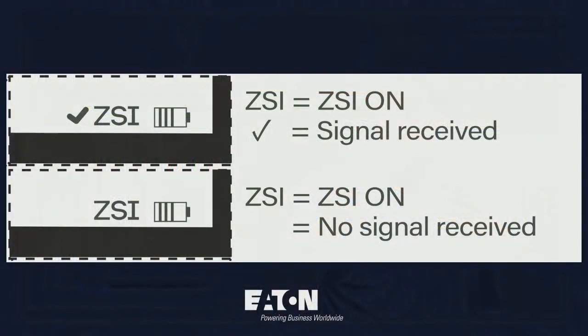So the reason that we have those three things is for those three reasons, and the last one is so you can tell if the breaker is properly wired into the system to where it's communicating with other breakers. So in the event that there's a fault in the system, this breaker could be talking to another breaker, saying, hey, do you see this fault? If that breaker says, nah, I don't see it, this breaker knows it can clear that fault right away.